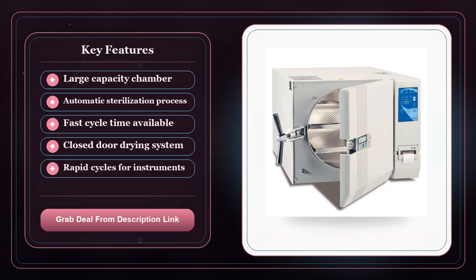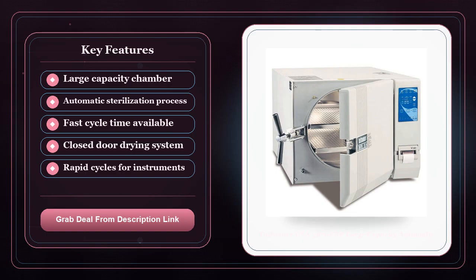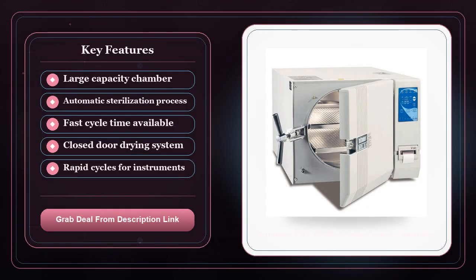Maintenance is another practical consideration. Tuttnauer's reputation for durability is solid, but any autoclave demands routine checks: water quality monitoring, gasket inspections, and periodic internal cleaning. The 3870 EAP's automatic cycle logging helps you stay on top of that, but you still need to schedule service visits or have a tech on call. If you're not comfortable setting up a maintenance contract, you might find yourself scrambling when the unit needs a seal replacement or a pressure valve calibration.